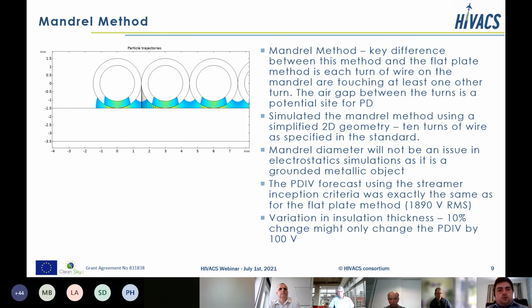So the next is to look at the Mandrel method. This method also has a predicted PDIV of 1890 volts RMS, so a very small difference compared to the flat plate. So it might be that the slight differences seen between the labs and the two test methods are really down to things like if there's any air gaps between the mandrel and the wire, or spacings between the wires, and also the noise levels and the detection systems that are used.